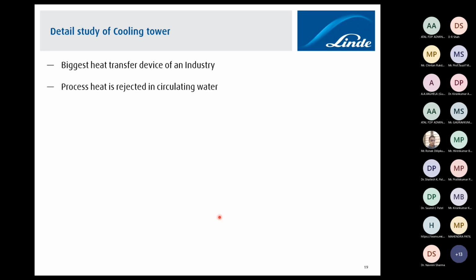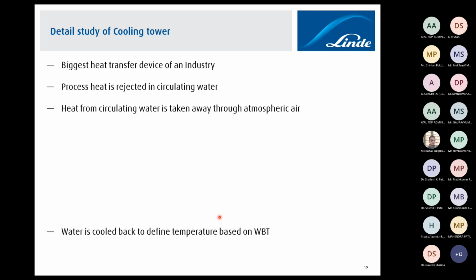Fine. Before we come to the types of cooling tower, let us understand what a cooling tower is and why it is needed. As you know, it is the biggest heat transfer device in an industry. It has a very large footprint. It works like a huge heat exchanger, and a very high amount of flow is taken care of at the cooling tower. Process heat is rejected into the circulating water through the various heat exchangers, and that comes back to the cooling tower. So heat from the circulating water is taken away through the atmospheric air. At the cooling tower end, all the heat is liberated in the form of atmospheric air, and this is how cooling takes place.